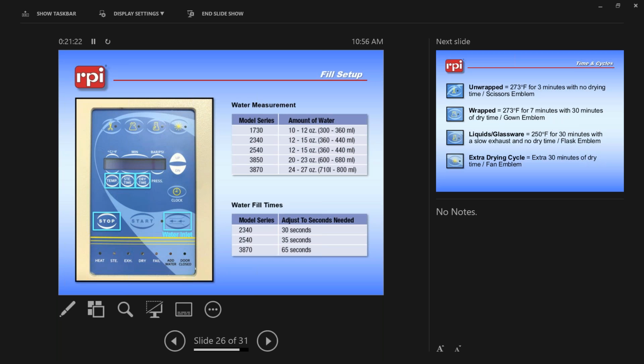For units that do not have a water pump, what you'll do to set the filling time is, once you have leveled the unit with the proper amount of water in it, you're going to power down the unit. You're going to push the water inlet key, which is on the bottom right there with 2 arrows on your keypad. You're going to push and hold that in while you power up the power switch. You're going to let go for just 1 second and then push it again. And you're going to keep holding it until the water inside the chamber reaches the fill groove. Once it does, let go of that water inlet key and then push stop on the unit and then power it down. That should be set for the future for the units that do not have water pumps.